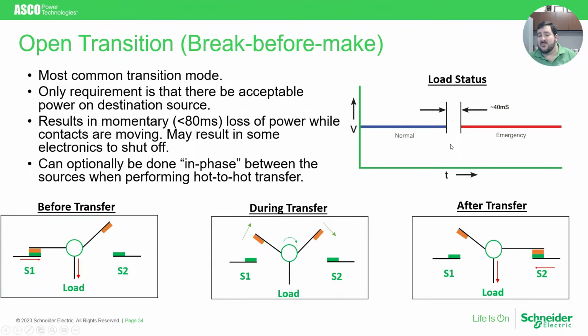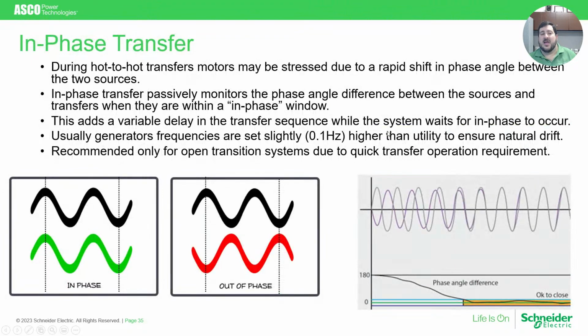However, this is still considered to be a very, very fast transfer and allows for a feature called in-phase transfer. In-phase transfer is used when you're transferring hot to hot, so during a test situation or when connecting back to utility after being on generator, and waits to initiate the transfer when both sources are synchronized to each other. As you can see here, the sources are out of sync, one source being the gray line and the other one being the pink line, and when they become in sync, that's when the transfer is initiated.